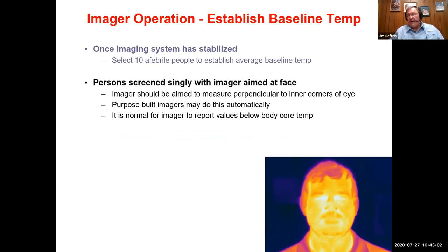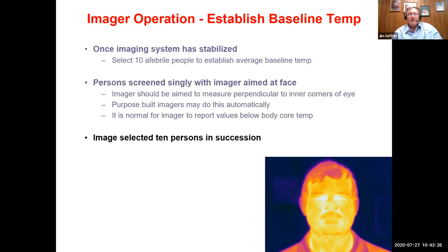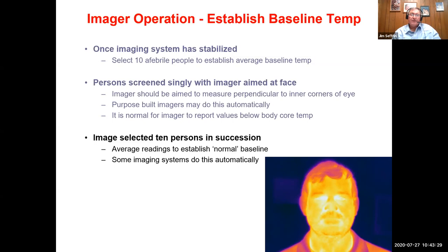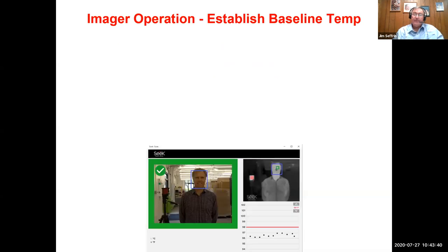Now, it is normal for your imager to report temperature values in this area of the face. It's called the inner canthus for one or inner canthi for two. These inner corners of your eye are going to give you a temperature that is very close to body core temperature. However, it's not uncommon for that temperature to be slightly below the anticipated 98.6 or 37 degrees Celsius. You image the selected 10 persons in succession, and you average the readings to establish a normal baseline. Now, some imaging systems will do this automatically. It really depends upon which one you're operating.